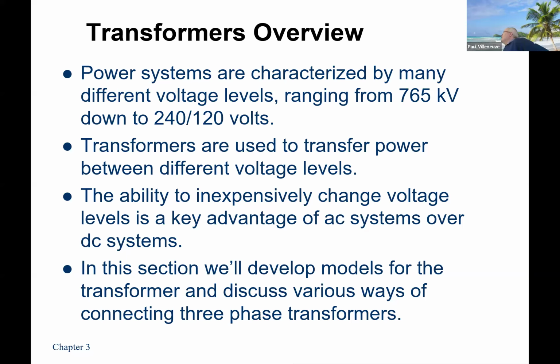Transfers various power levels. Notice I said power levels. Is that the right term? The power isn't transformed, because I don't take power from a higher level to a lower level. I take the voltage from a higher level to a lower level. And conversely, the current is the reciprocal of that. It would go from a lower level to a higher level. So a transformer is essentially a constant power device, meaning almost all the power that goes into the transformer comes out of the transformer. Very highly efficient devices, 99% efficient at full load, not a lot of losses. And so, like I said, oftentimes we'll assume that they're 100% efficient to make our work a little bit easier.